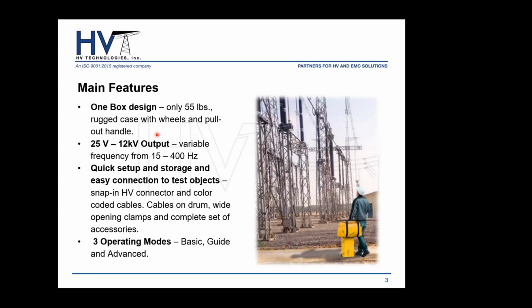The quick setup and storage has very easy connections with snap-in HV connectors and color-coded cables. So we try to minimize connection errors so that tests run more smoothly. All the cables come on cable drums. The clamps that are equipped with the instrument are wide opening clamps, so you can connect to most transformers, bushings, capacitors, you name it. And it also has a wide array of accessories that you can also use for temperature and so on, but we'll get into that later. We also will get into the three operating modes of the MIDAS Micro. It has three modes: basic mode, guide mode, and advanced mode. We'll get into that later on.